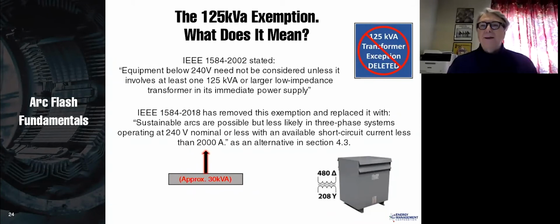What does that mean? That was kind of a famous exemption that said if you have mostly a 208 volt transformer and it is smaller than 125 kVA, you don't even need to do an arc flash study. It does not have the ability to give you a second degree burn. And so you could slap a sticker on anything downstream of that transformer, your panel boards, switchboards, anything downstream, that basically said you were level 0 and that you didn't need to worry about arc flash.